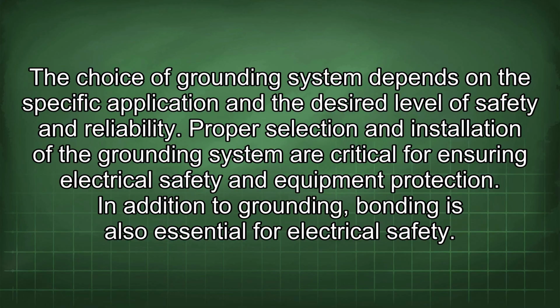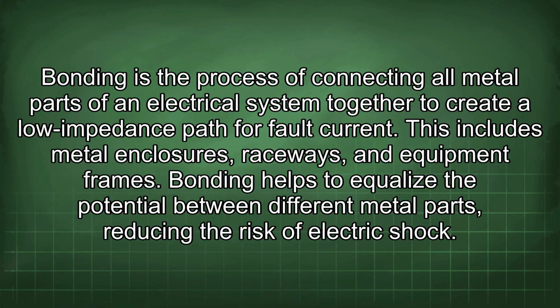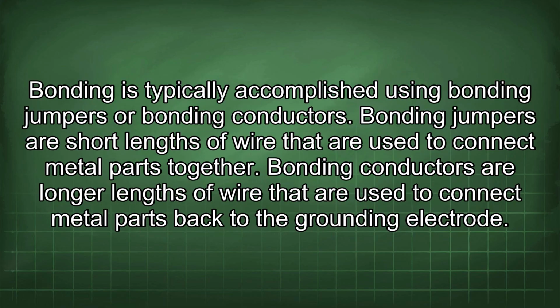In addition to grounding, bonding is also essential for electrical safety. Bonding is the process of connecting all metal parts of an electrical system together to create a low impedance path for fault current. This includes metal enclosures, raceways, and equipment frames. Bonding helps to equalize the potential between different metal parts, reducing the risk of electric shock. Bonding is typically accomplished using bonding jumpers or bonding conductors.